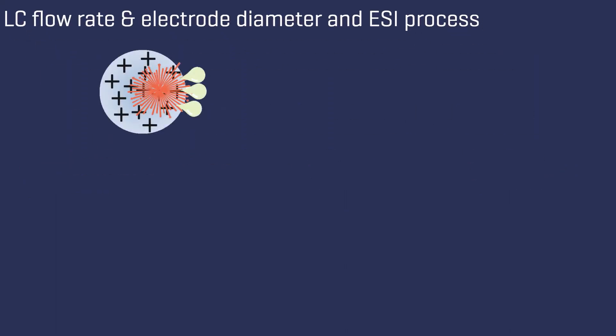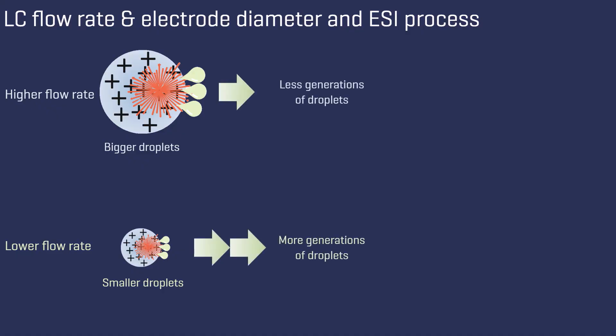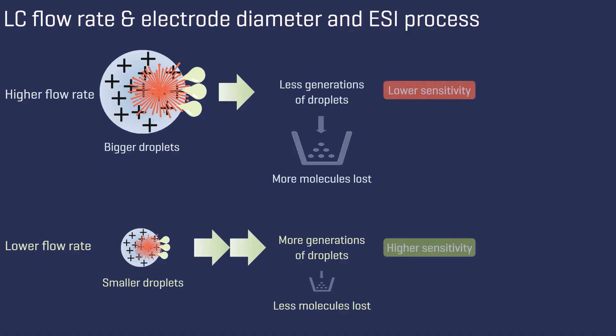The flow rate not only impacts the optimal source parameters, but also the size of the initial droplets. A lower flow rate results in smaller initial droplets, which evaporate more easily, allowing for the formation of more generations of droplets. As a consequence, fewer molecules will be lost for analysis and more molecules can be detected. When analyzing an analyte at a given concentration with different flow rates, the sensitivity can be higher at lower flow rates.